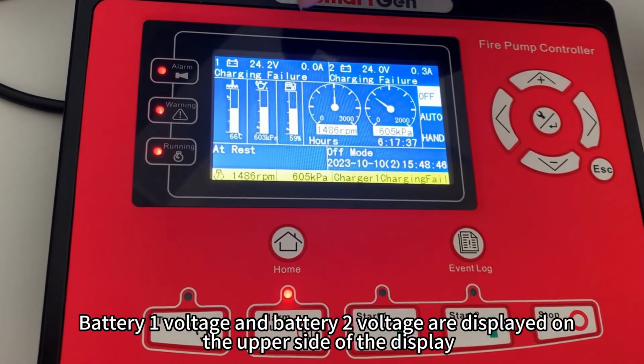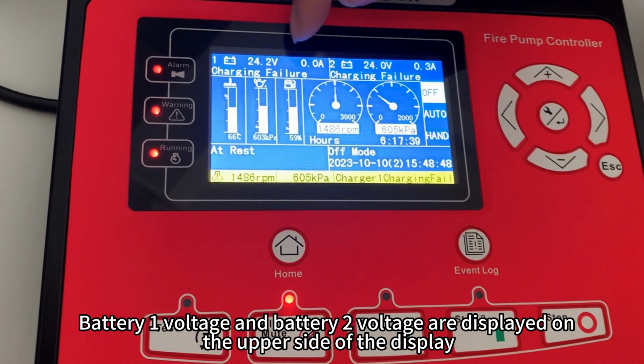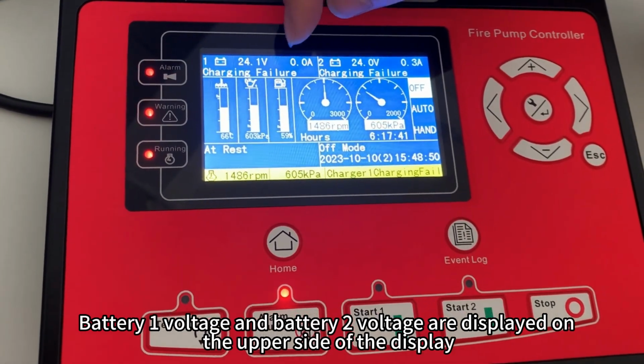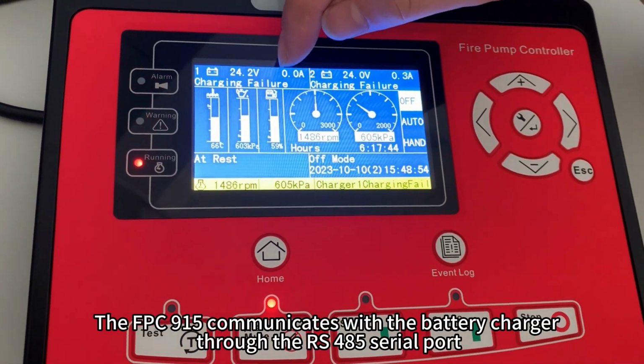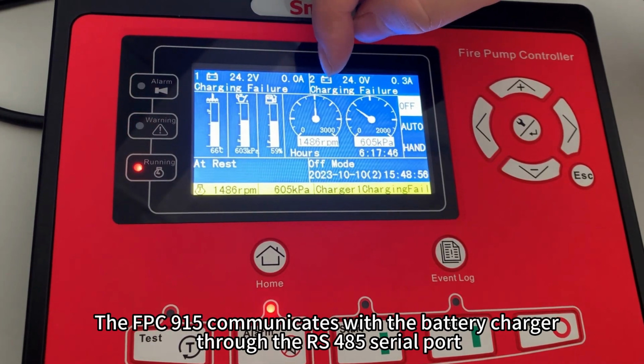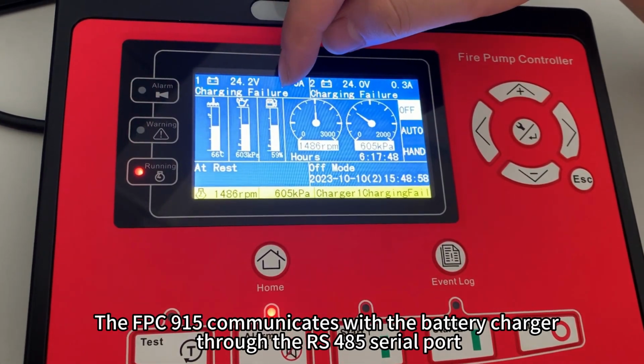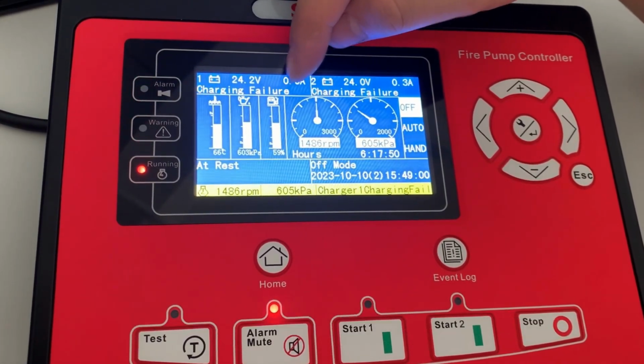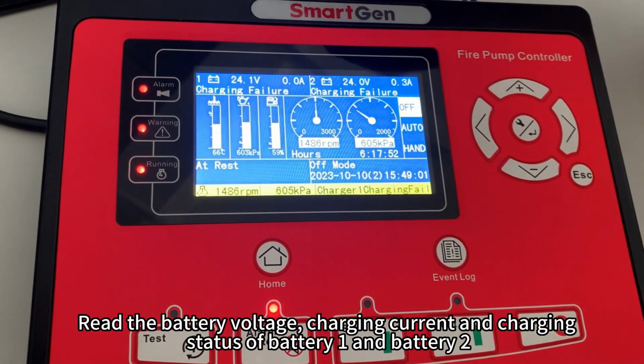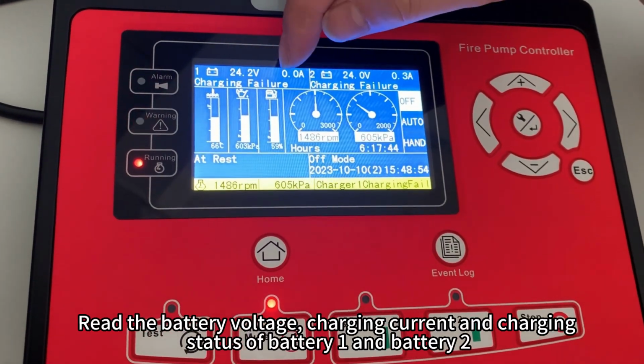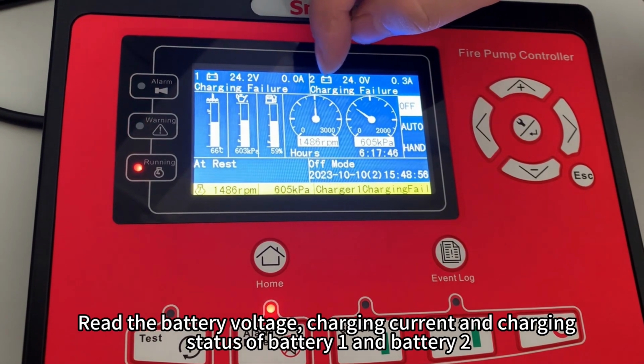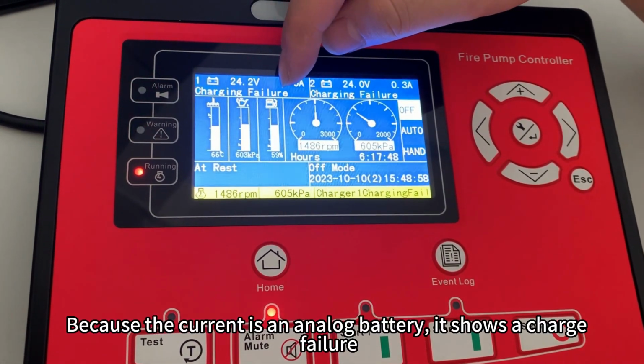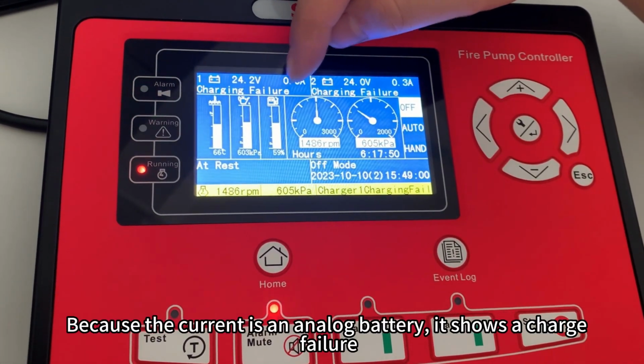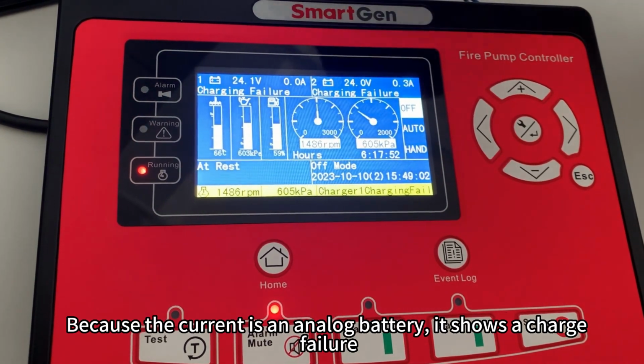Battery 1 voltage and battery 2 voltage are displayed on the upper side of the display. The FPC 915 communicates with the battery charger through the RS485 serial port. It reads the battery voltage, charging current and charging status of battery 1 and battery 2. Because the current one is a simulated battery, it shows a charge failure.